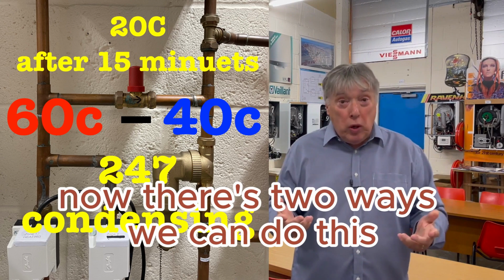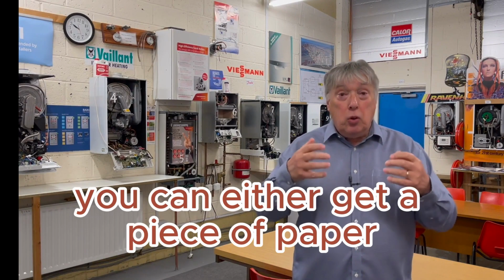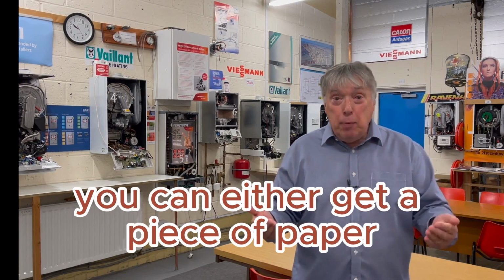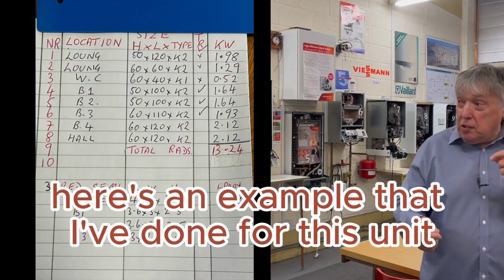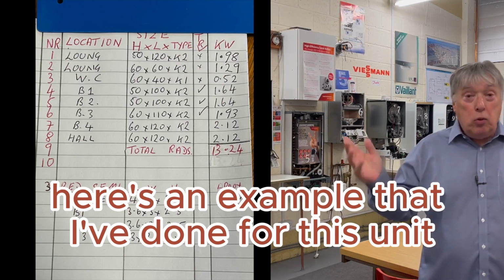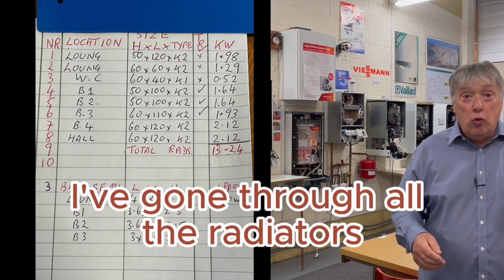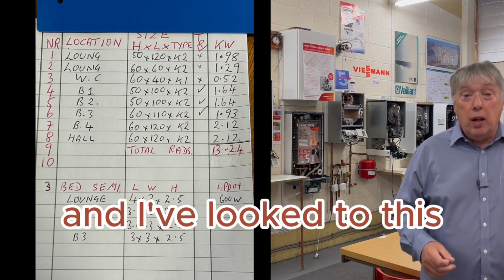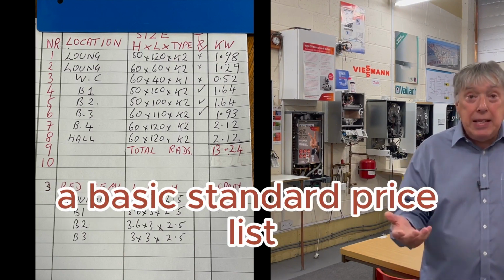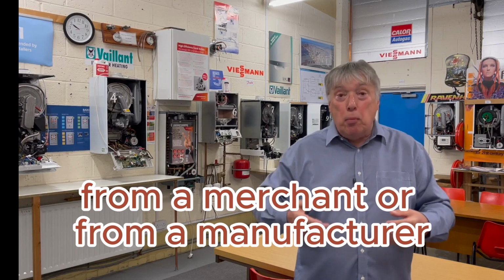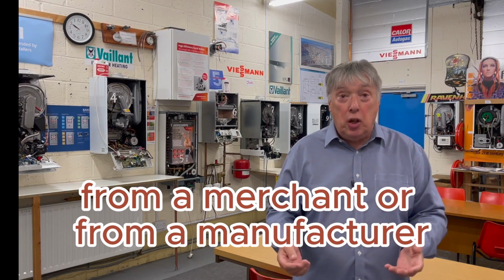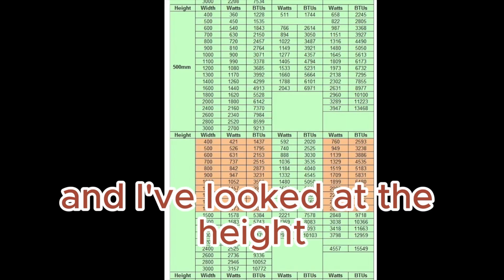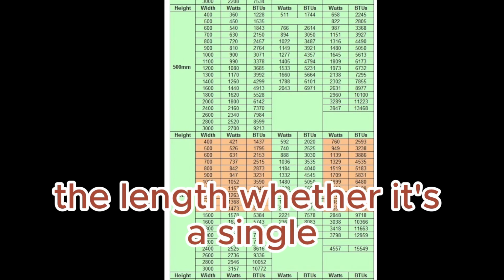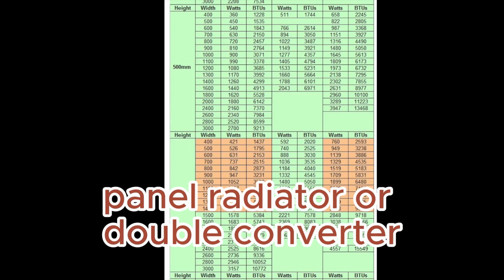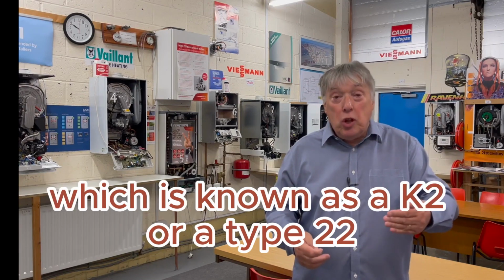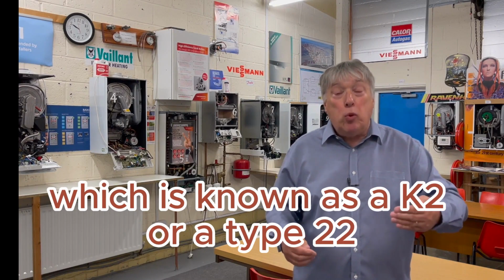Now, there's two ways we can do this. You can either get a piece of paper. Here's an example that I've done for this unit. I've gone through all the radiators and I've looked at a basic standard price list from a merchant or from a manufacturer, and I've looked at the height, the length, whether it's a single panel radiator or double convector, which is known as a K2 or a type 22.